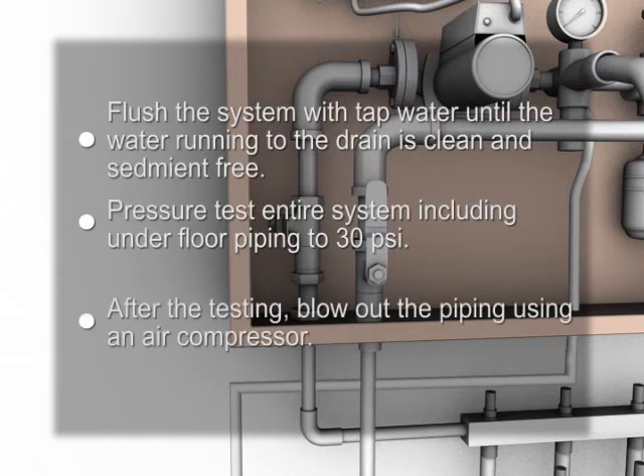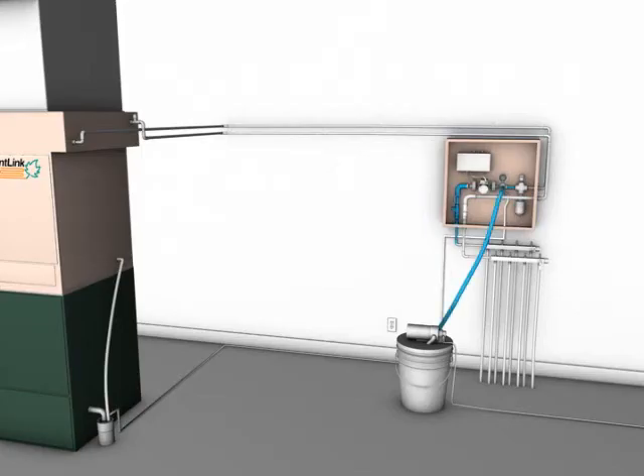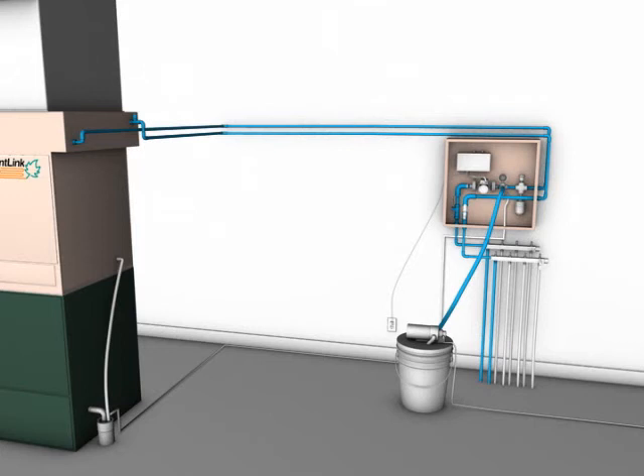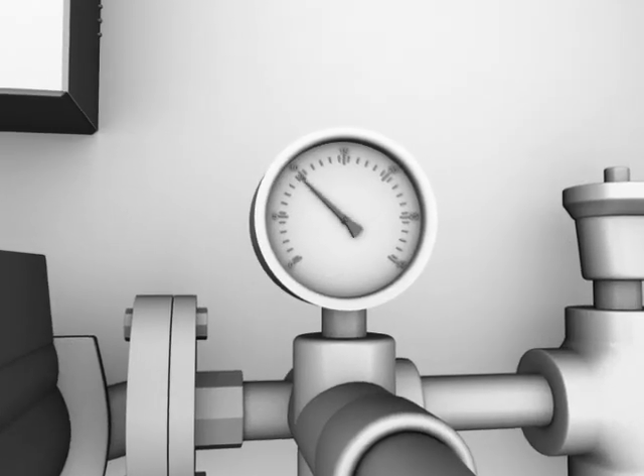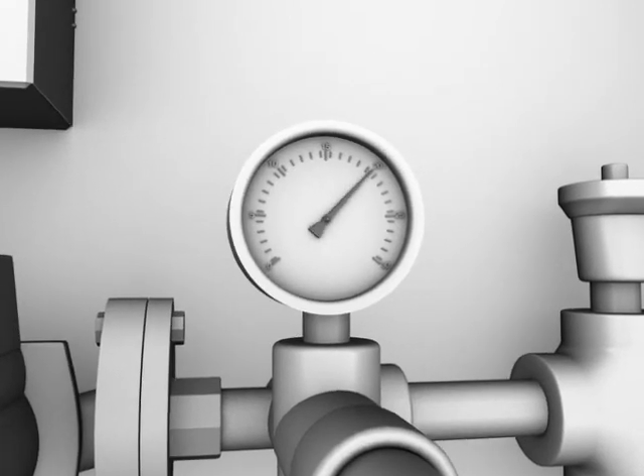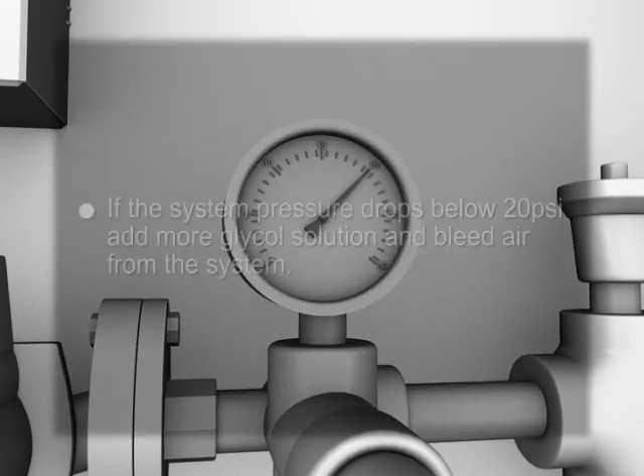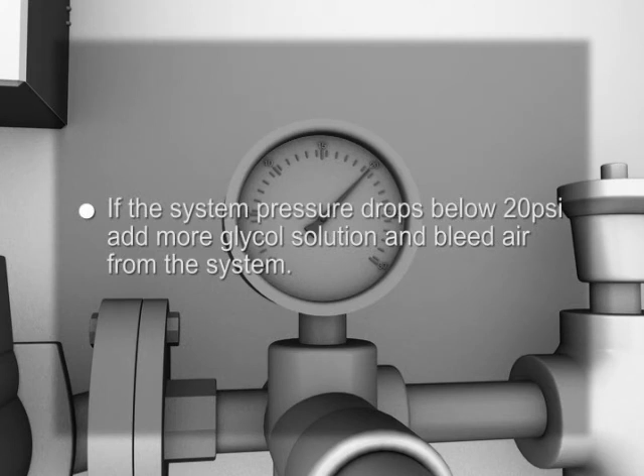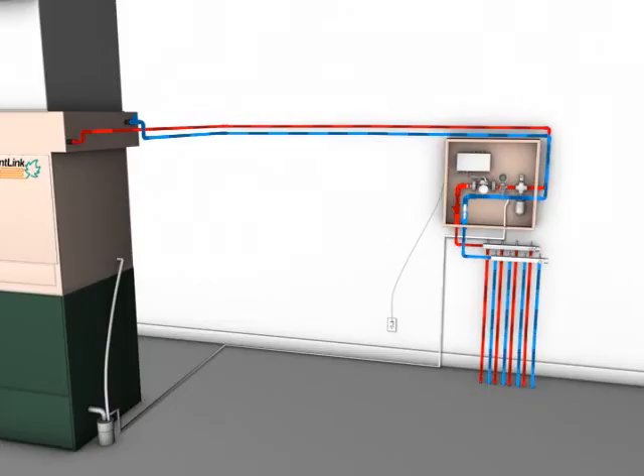After the system is tested, blow out the piping using an air compressor to ensure that all water is removed from the in-floor piping. Charge the system with a solution of 25% inhibited propylene glycol and soft water. Plug in the control panel power cord and adjust the thermostat so that the pump operates. Bleed all air out of the entire system one floor loop at a time and continue to charge the system with the glycol solution until the system pressure registers 20 psi on the control panel pressure gauge. If the system pressure drops below 20 psi, add more glycol solution and bleed air from the system.